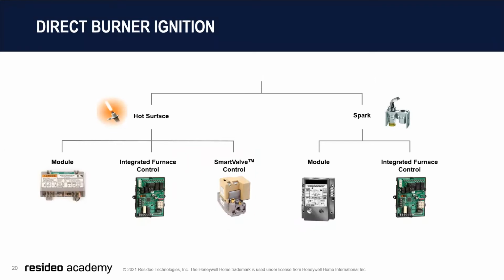Direct burner ignition is usually handled either through a sparker, which is going to be through a module or an integrated furnace control, or a hot surface, which is going to be a module, integrated furnace control, or sometimes directly from the smart valve.